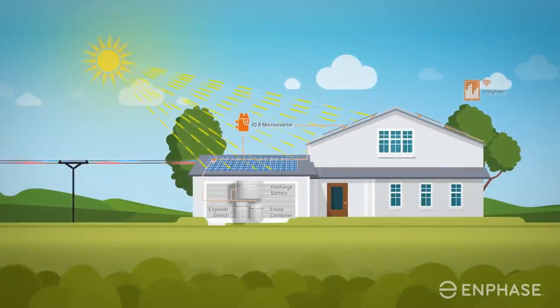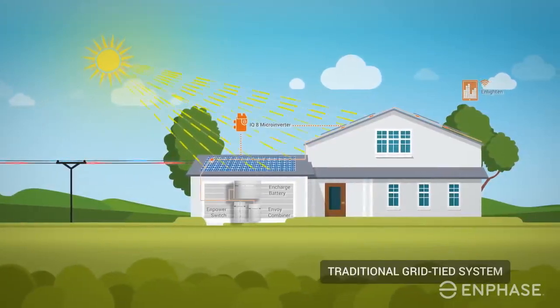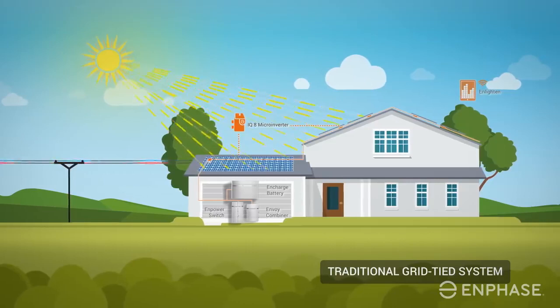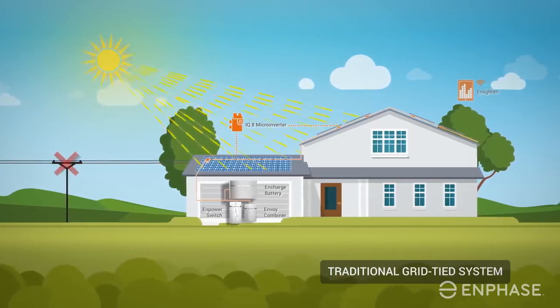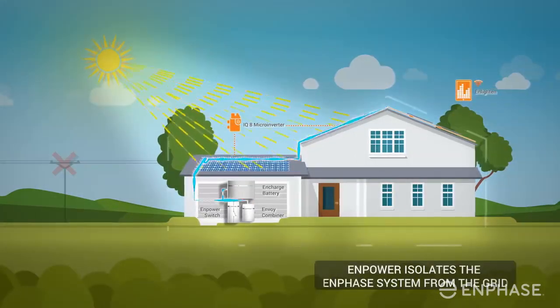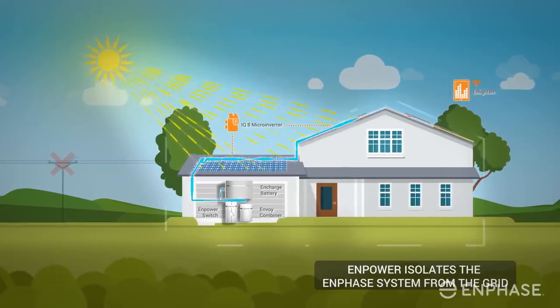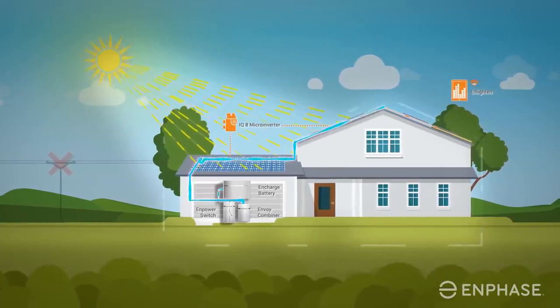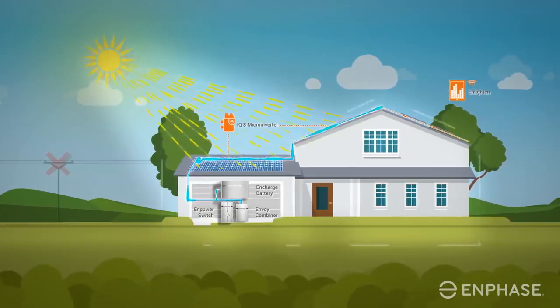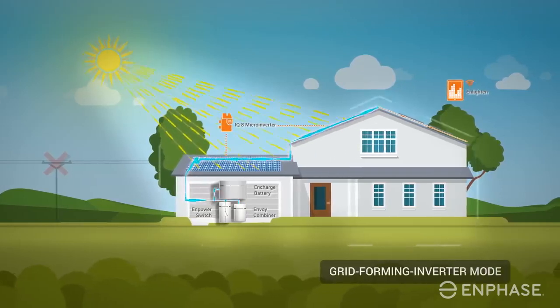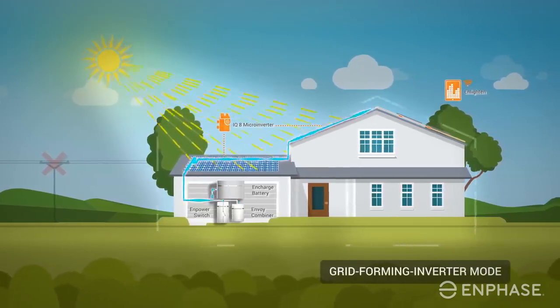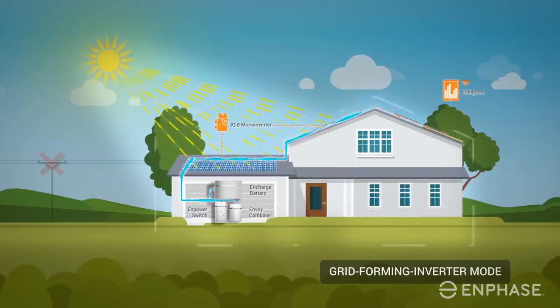When connected to the grid, the Enphase system works as a traditional grid-tied system. But in the event of a grid failure, Enpower senses the outage and isolates the Enphase system from the grid connection. The IQ8, however, continues to harvest solar energy by transitioning into grid-forming inverter mode. All this happens autonomously in the blink of an eye.